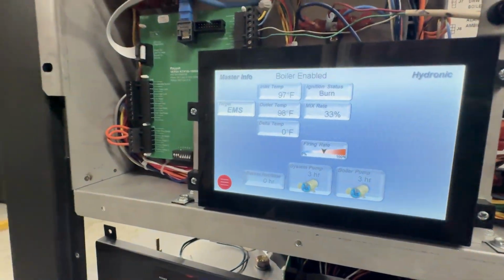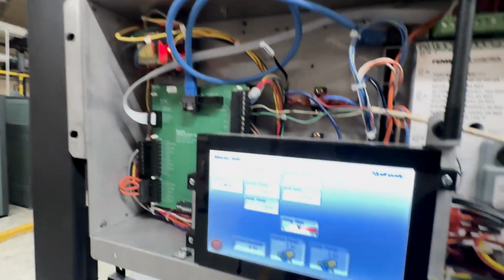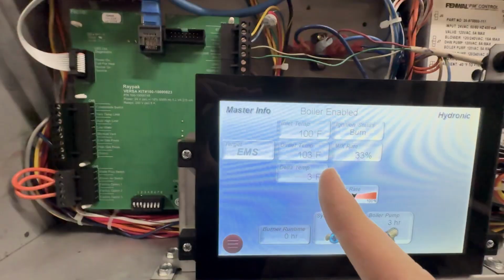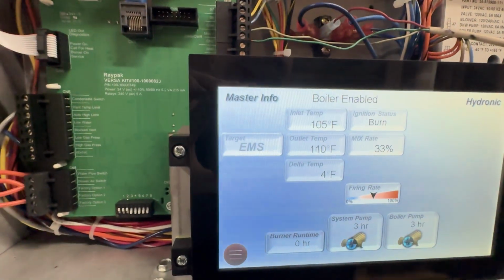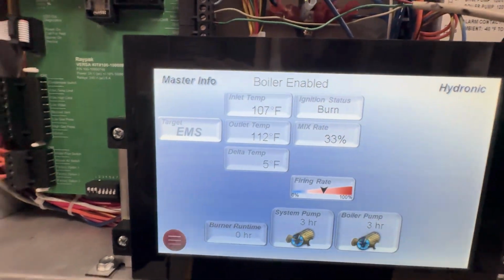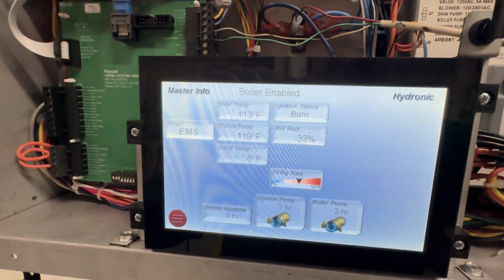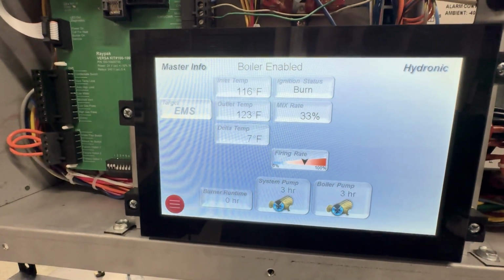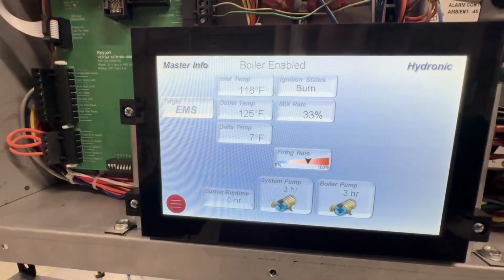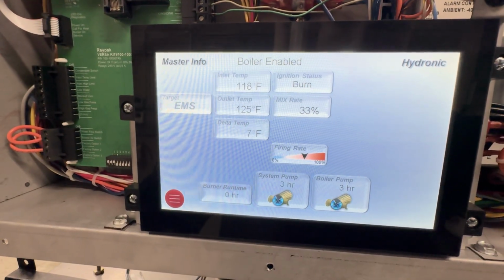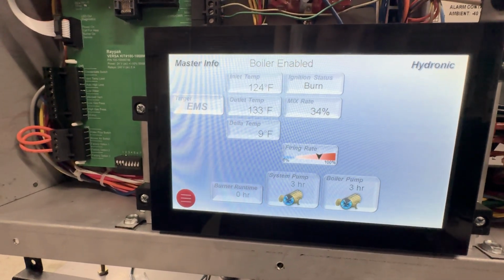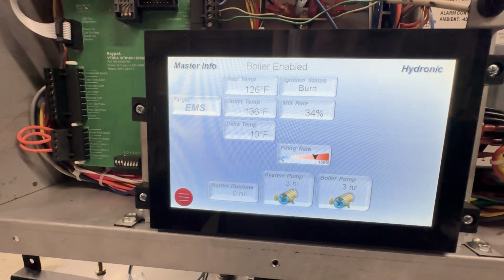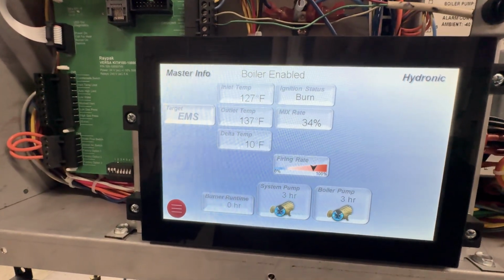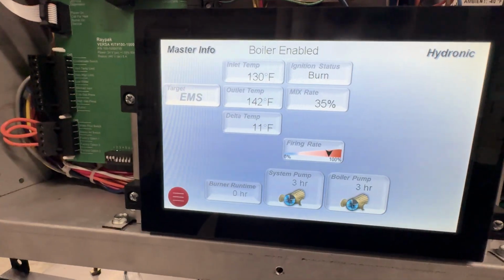Moving on to burn. So remember, we set that high limit over there to 170. What we're looking to see is that once this outlet temp hits 170 plus or minus 5 degrees, the boiler will trip on automatic high limit. We can see the firing rate ramping up. We're at probably about 80%.